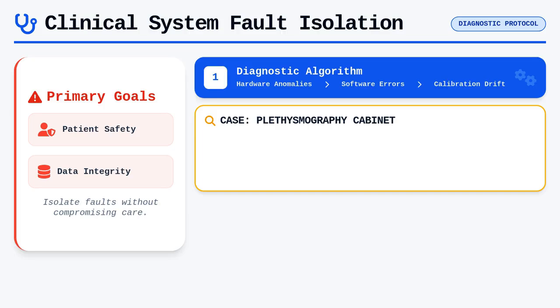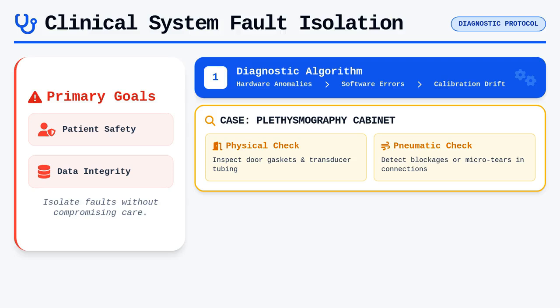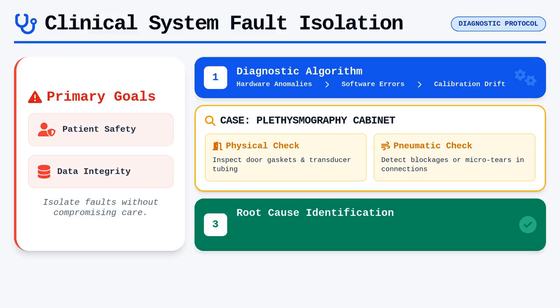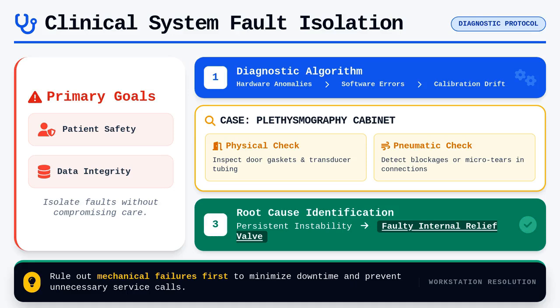For instance, if you encounter a plethysmographic cabinet that refuses to seal or loses pressure, your first step is a logical inspection of the door gaskets and the integrity of the pressure transducer tubing. A simple leak can mimic significant physiological changes, so systematically check the pneumatic pathways for blockages or micro tears in the flexible connections. If the cabinet pressure remains unstable despite these checks, the issue likely stems from a faulty internal relief valve rather than a user error. By ruling out simple mechanical failures first, you minimize downtime and prevent unnecessary service calls that could have been resolved at the workstation level.